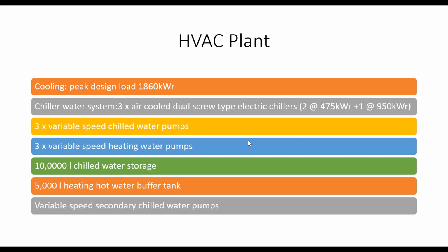The HVAC plant has been designed to have a peak design load for cooling. The 3 chillers, screw-type electric chillers, have been selected to enable either one small chiller to be used if required in the shoulder seasons, and 1 or 2 of any combination of 2 chillers to be used to enable for the variability in the cooling load because of the seasonality at Qd. The chilled water and heating water pumps are all variable speed. There's chilled water storage, heating hot water buffer tanks, variable speed secondary chilled water pumps, etc.